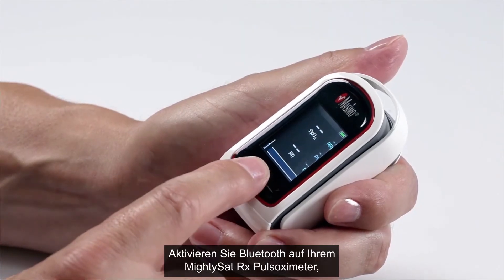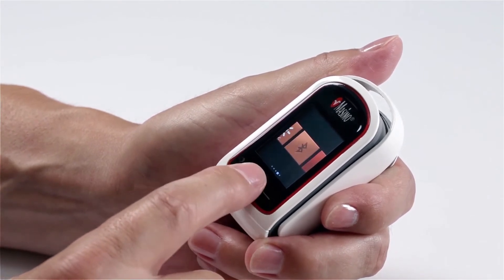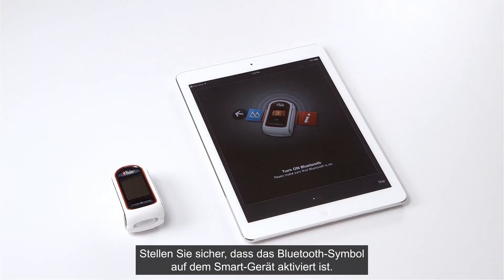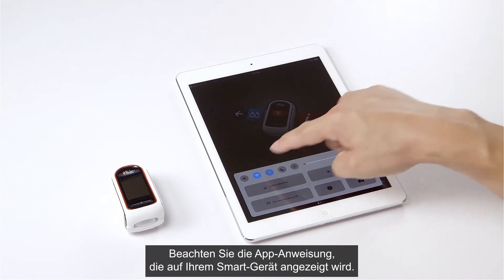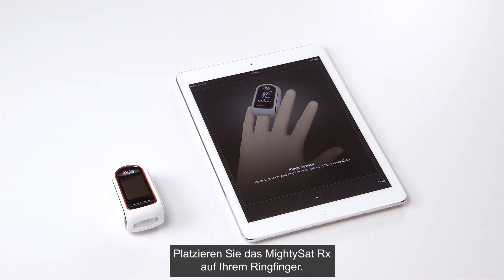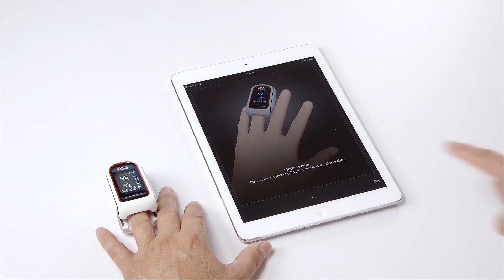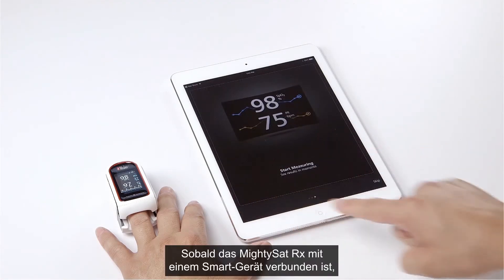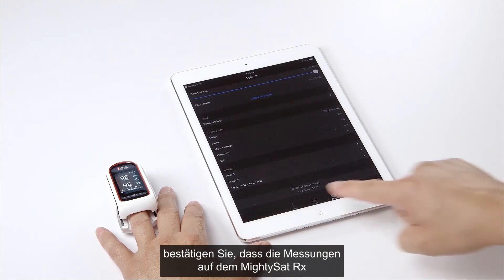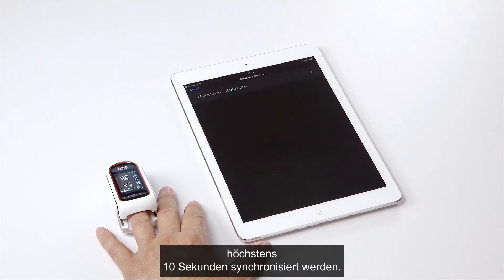Turn on Bluetooth on your MightySat Rx pulse oximeter. Ensure Bluetooth is also enabled on the smart device, following the app instructions as shown. Place the MightySat Rx on your ring finger. Once connected to the smart device, confirm that the readings on the MightySat Rx and the Masimo Professional Health app are synchronized without a delay greater than 10 seconds.